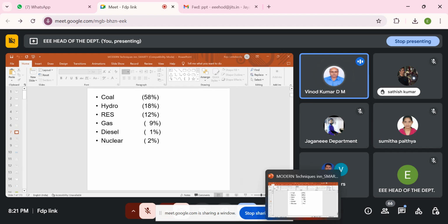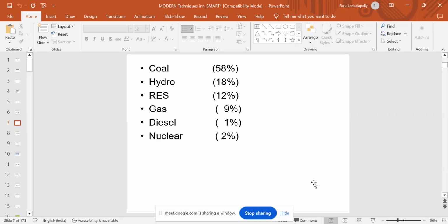By sitting at the load dispatch center, we get several data. We can conduct this using the SCADA system, supervisory control and data acquisition system. In supervisory control, it is nothing but real remote control. So, sitting at a load dispatch center at Hyderabad, I can control nearby districts like Warangal, Karimnagar, or Ramagundam. We can switch on or switch off the circuit breakers, or switch on or off the shunt capacitors which are connected. We can do this remotely, and by using RTUs we get the data. So supervisory control is the heart of the load dispatch center, that is why we call the SCADA system the heart of the energy management system.